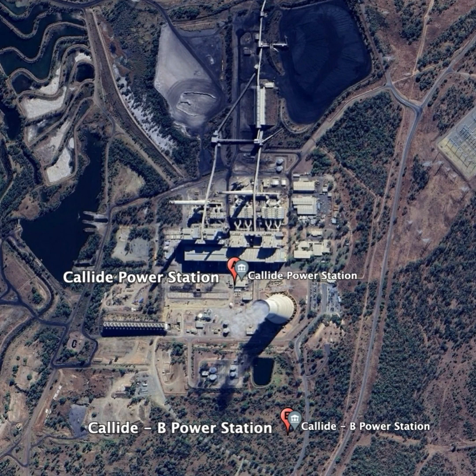At 2:10 p.m., AEMO gave permission to commence load restoration from loads that were shed due to under-frequency relay operations. AEMO also gave permission for all available units to resynchronize to the grid and reconnect, with Yarwun Cogen reconnecting at 2:28 p.m., Stanwell units starting at 2:31 p.m., and the Gladstone Power Station unit starting from 2:52 p.m. At 3:03 p.m., the Callide substation was re-energized, and by 3:40 p.m., all 275 kV feeders were reconnected.